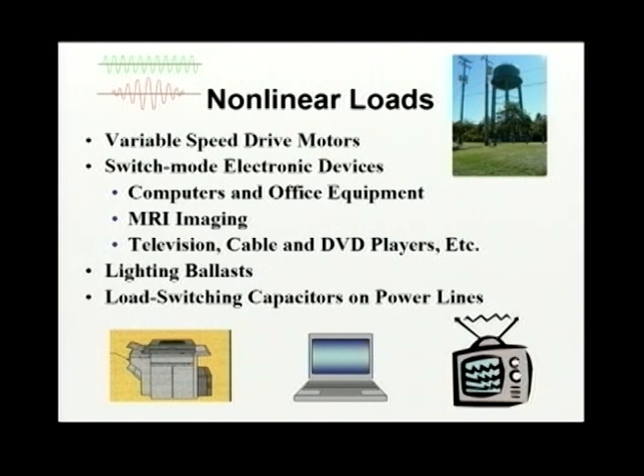Direct current is current which travels in only one direction, as from a battery. Electronic devices change the frequency of AC current to speed up or slow down a process or signal. Variable speed drives, switch mode electronic devices such as copy machines, MRI or magnetic resonance imaging, TV, cell phones, digital clocks, radios, some types of halogen and fluorescent lighting ballasts, load switching capacitors on power lines, and hundreds of other electronic controls use nonlinear loads and contribute to electrical pollution.